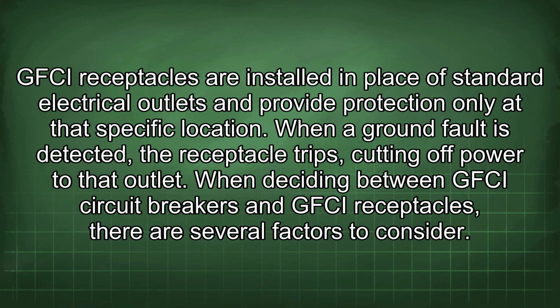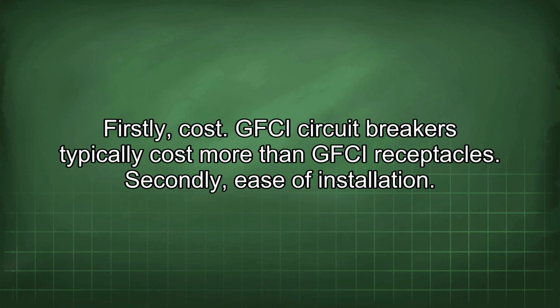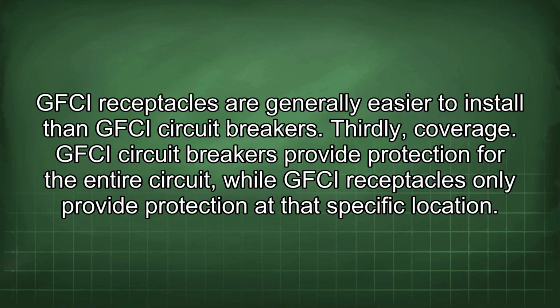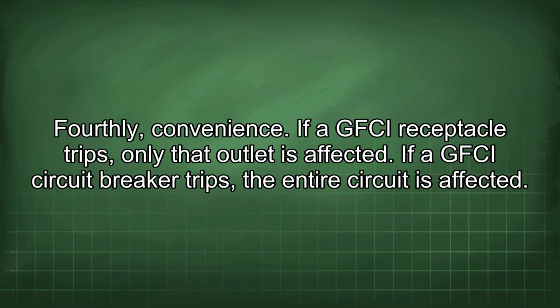When deciding between GFCI circuit breakers and GFCI receptacles, there are several factors to consider. Firstly, cost. GFCI circuit breakers typically cost more than GFCI receptacles. Secondly, ease of installation. GFCI receptacles are generally easier to install than GFCI circuit breakers. Thirdly, coverage. GFCI circuit breakers provide protection for the entire circuit, while GFCI receptacles only provide protection at their specific location. Fourthly, convenience. If a GFCI receptacle trips, only that outlet is affected. If a GFCI circuit breaker trips, the entire circuit is affected.